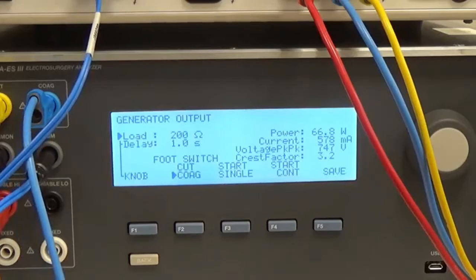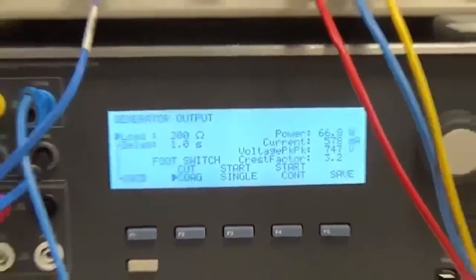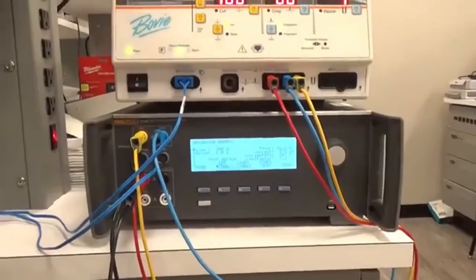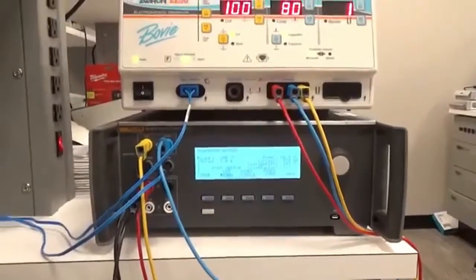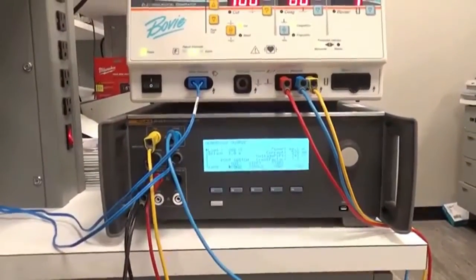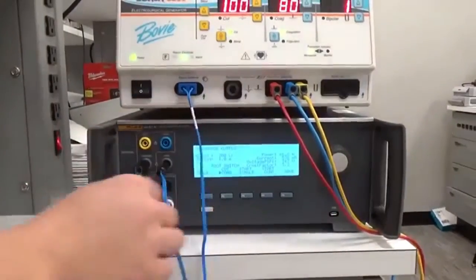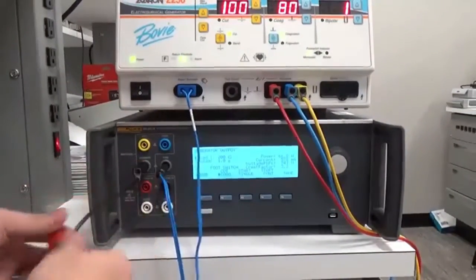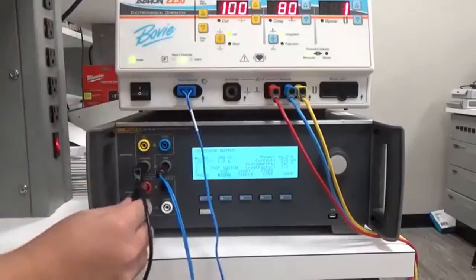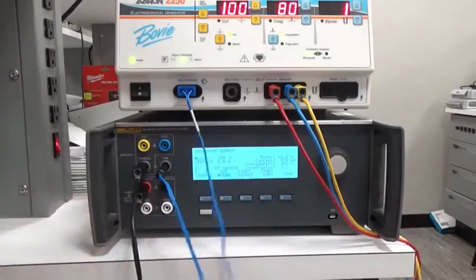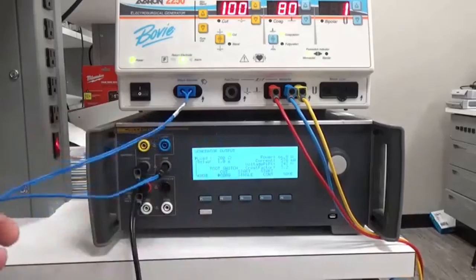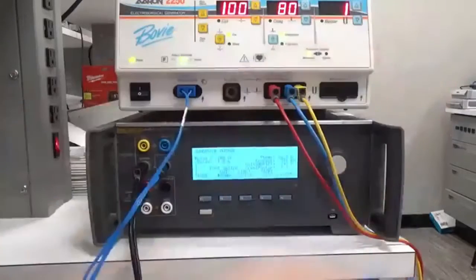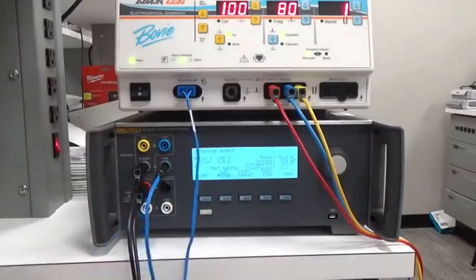So this is one way to connect the two devices together. I'm actually going to show you another way. And what we need to do is we actually need to disconnect most of these. I'm going to leave common and the variable high jumped, and I'm going to leave my ground electrode, or return electrode, connected as well.